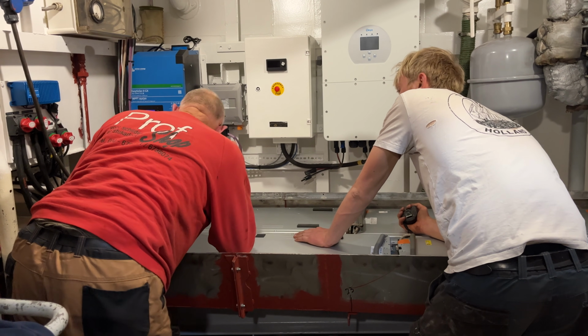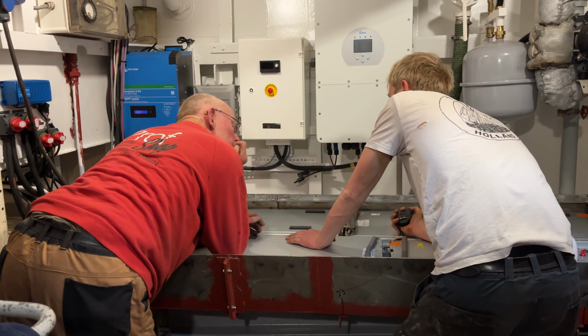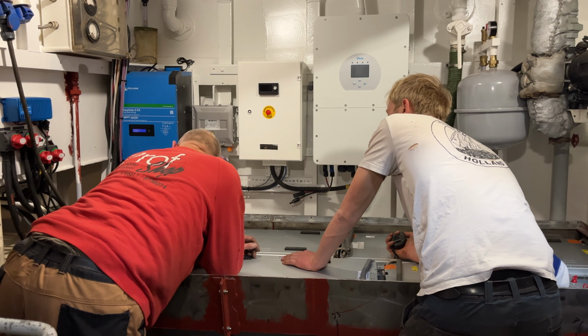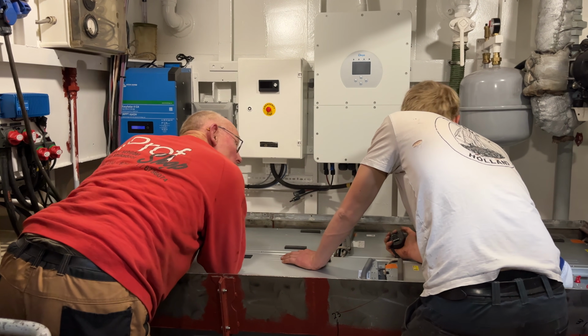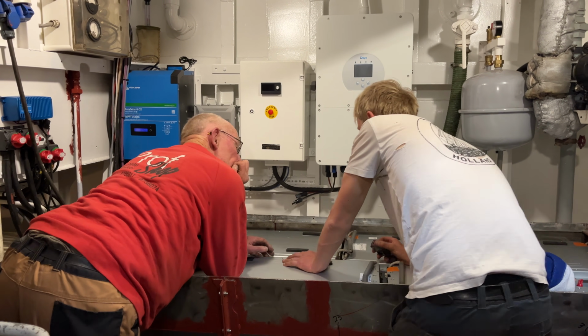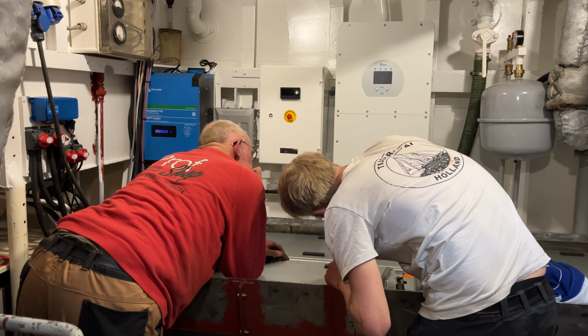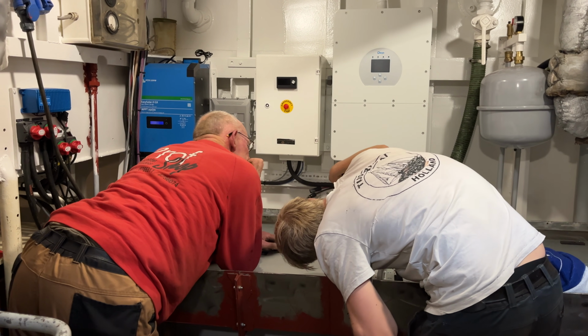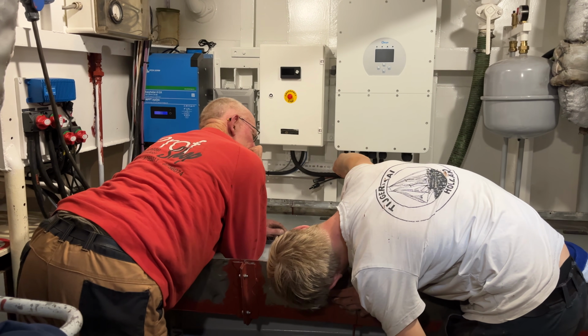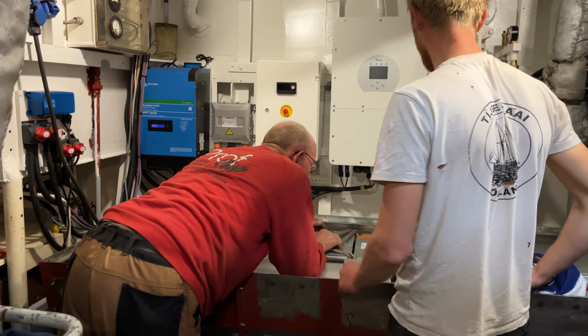We have almost spent this entire video on our first line of defense, making thermal runaway unlikely in the first place. But we still have layer 2 and 3, which come into place when something actually goes wrong inside the cells. The second line of defense is containing a starting runaway to that one module. We have 4 modules in total, and losing one of them is of course far better than losing all 4. The BMS helps here as well. It keeps monitoring the temperatures and will shut down charging and discharging if a runaway is detected. But it cannot stop a runaway once it has started inside a cell.